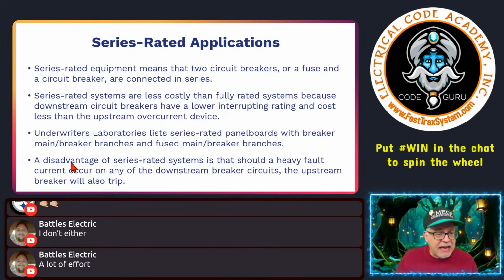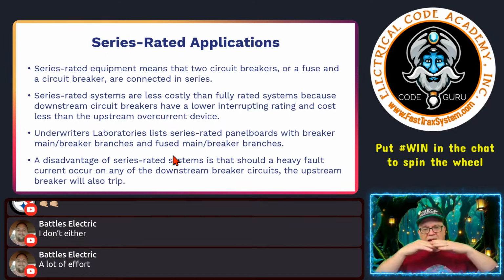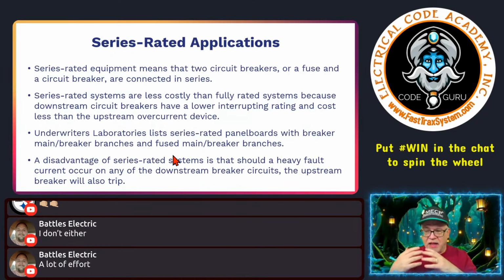Now, a disadvantage of series rated systems is that should a heavy fault current occur at any of the downstream circuit breakers that are rated less than the main, the upstream breaker will also trip. So this is a problem. If a heavy fault occurs at the downstream one, there's a high probability that, when it's series rated, it takes out the one upstream. That is not conducive to selective coordination, because we do not want to take out the one upstream. So that is one disadvantage of a series rated system.